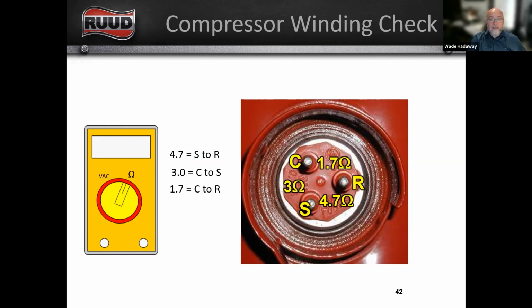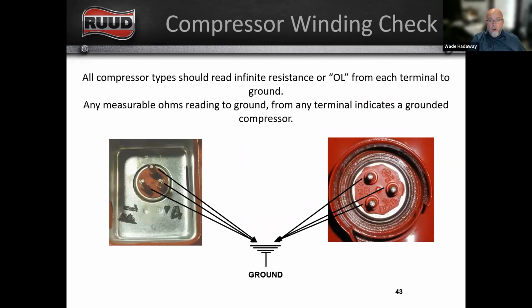So the other compressor check that you can do on the windings is you want to make sure that each one of these terminals does not have any resistance from each of those terminals to ground. And a ground can be sanding off a nice little clean spot on a refrigerant line. Anything that is a good ground, and your refrigerant lines make a good ground. There's a grounding lug on each one of these units that you can use, but you want to make sure that you get nothing read. It'll read OL, and that is infinite, meaning it doesn't read anything. If you get any sort of a reading, even a 0, that tells you that winding in this compressor is shorted to ground or has a direct short.